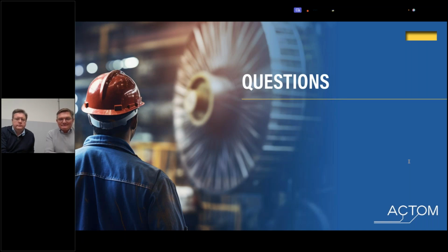Our next question is again from Mr. John Wilson. He's asking, are any bespoke lower power CTs and VTs available to implement digital substation technology? Yes, that's something we've been looking at. It's good because quite a few of our customers and users have shown interest in that. Due to the design of the solid dielectric switchgear, it becomes quite a simple matter to plug in a low power voltage transformer. You have the option of plugging it into the screened separable connector as a replacement for the back insulating plug. But we could also incorporate that on the tee-off. There's a tee-off bushing, an inner cone bushing, that we use to connect the conventional VTs through a screened inner cone connector, and those could simply be plugged in and used as an alternative.